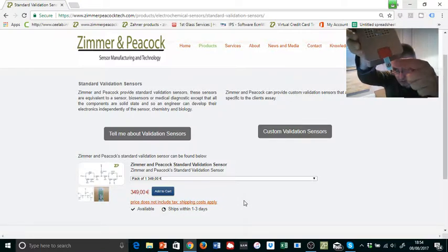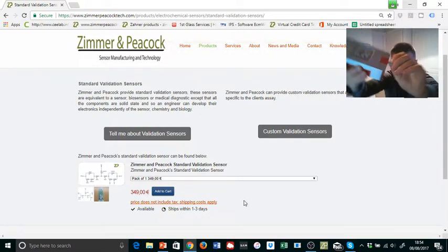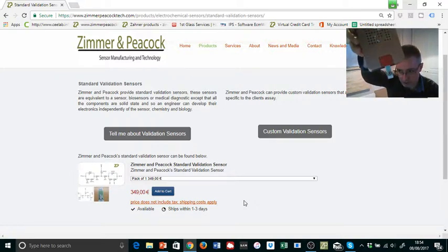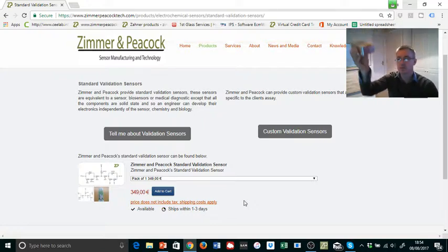So here's an electrochemical cell. When you put antibodies or enzymes on it, it becomes an electrochemical sensor. So what we're trying to do is come up with an engineering solution which is made of capacitors and resistors that mimics that, but it means that an engineer does not have to be handling solutions. So that's a high level. We're trying to make a circuit that's equivalent to the sensor or the assay, but it's only got capacitors and resistors in it, and an engineer can just slot it in and check it.